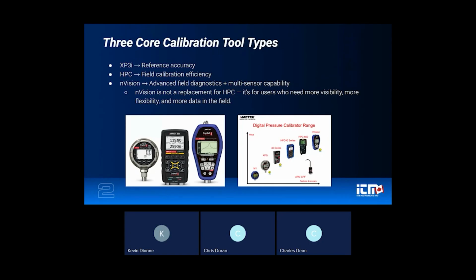And the nVision takes things a step further. It's designed for advanced field diagnostics. It has multi-sensor capability: the temperature, the voltage, the milliamps. And it's used when you need more visibility into your system: multiple pressures, different ranges, deeper analysis. It's a tool that's built for that job.